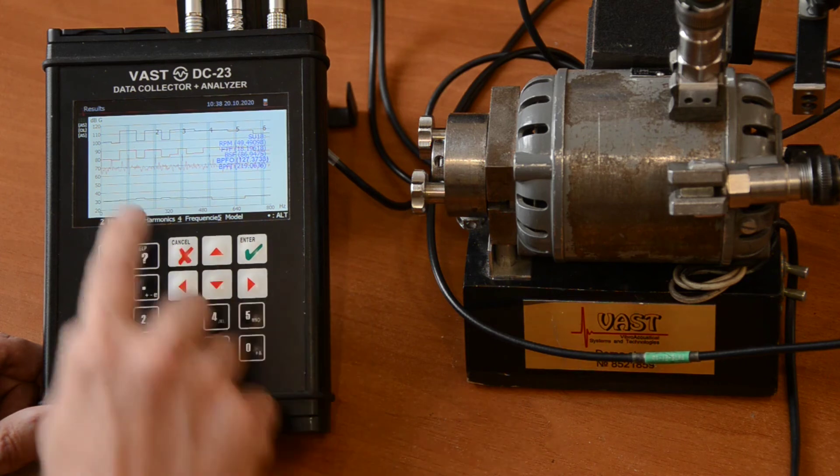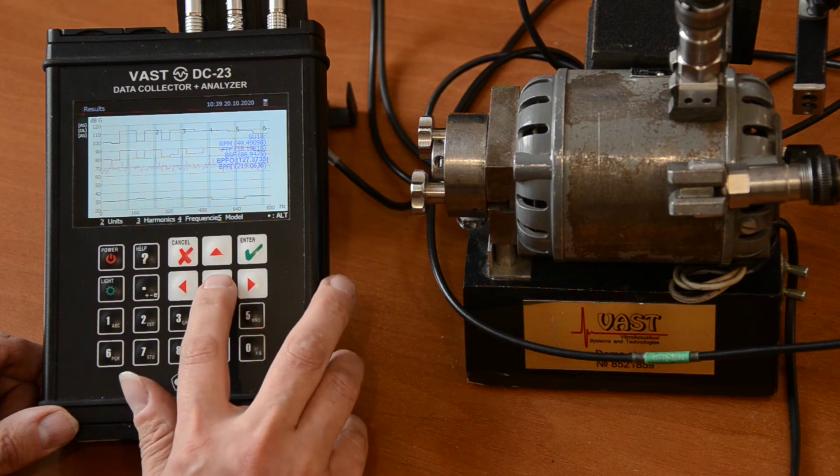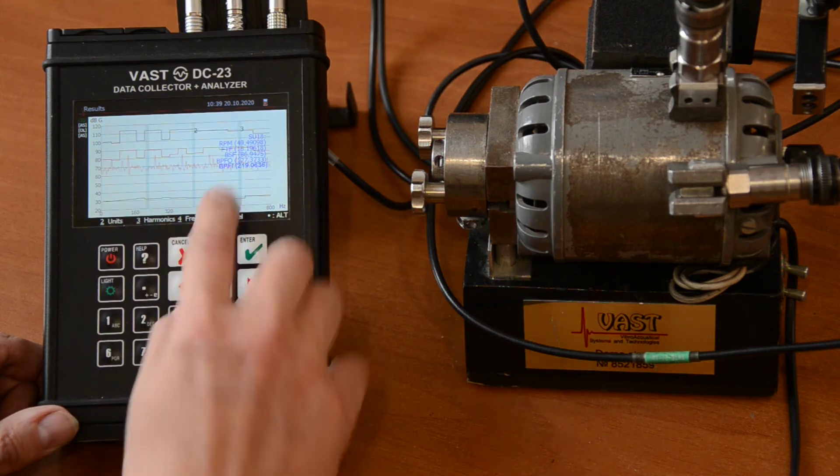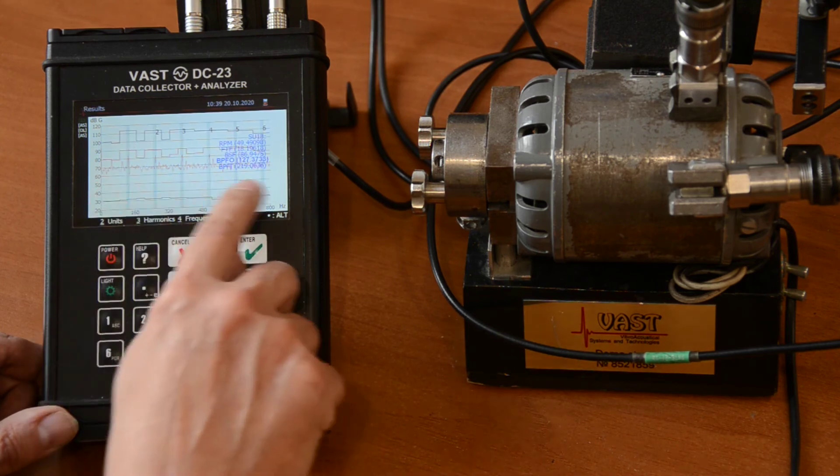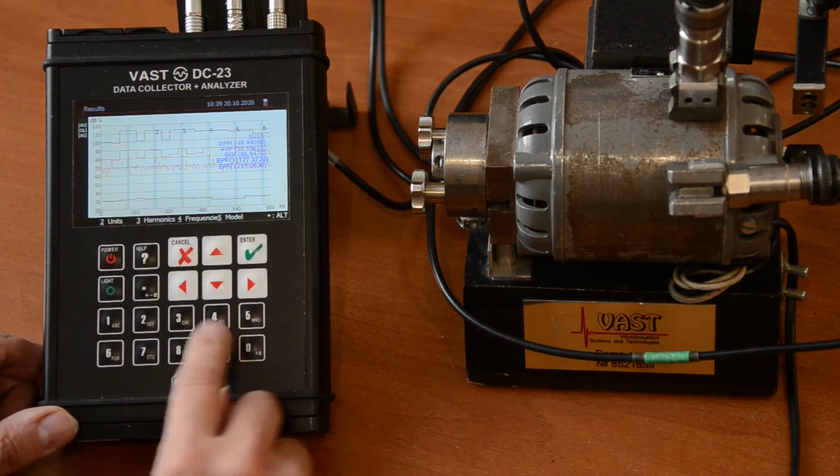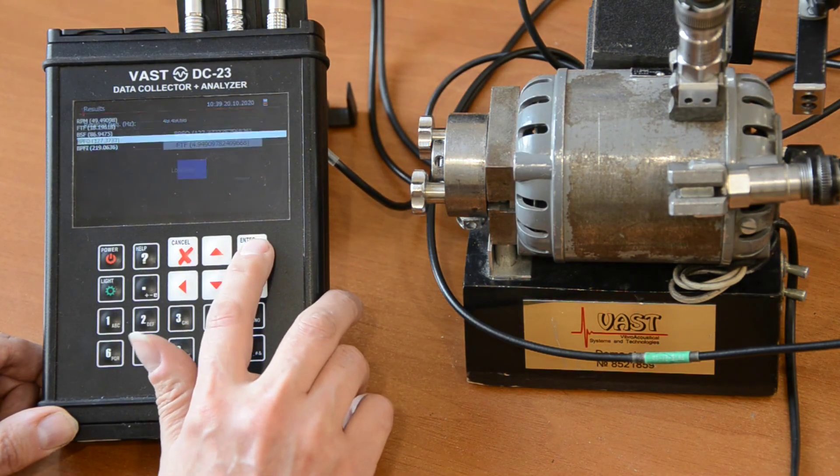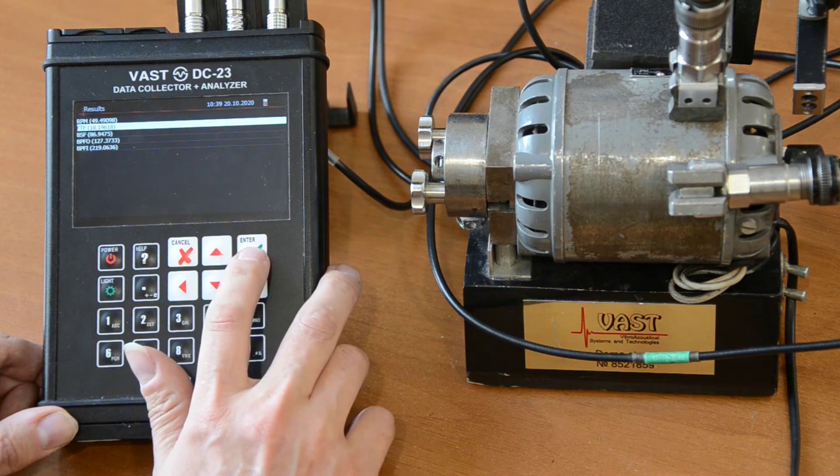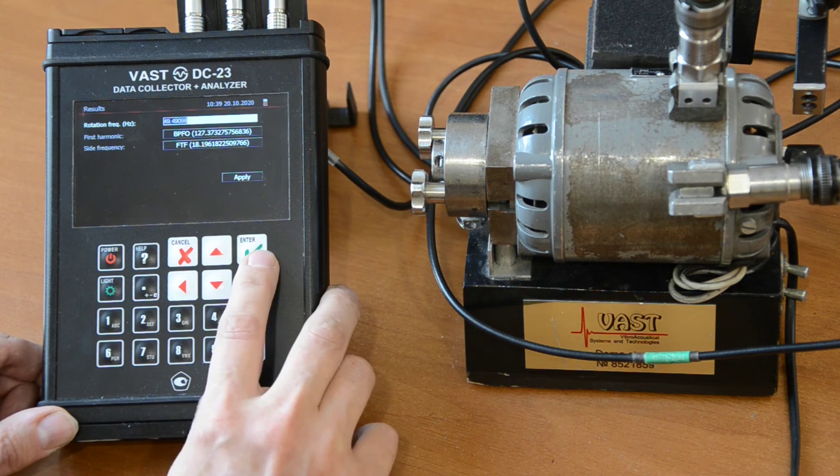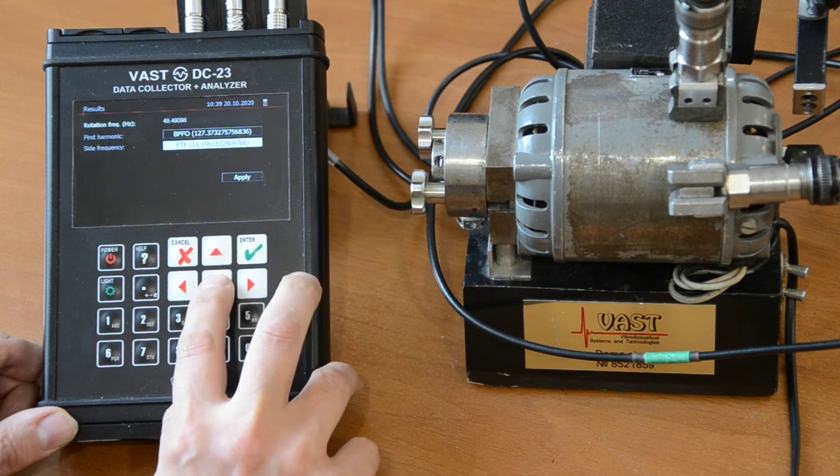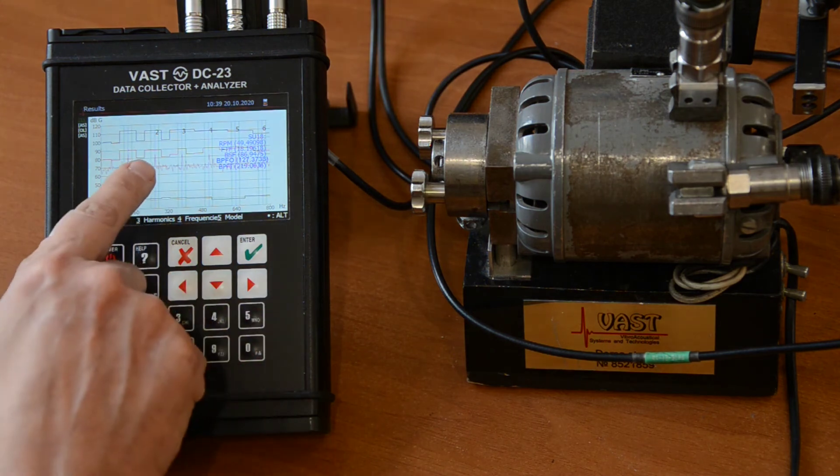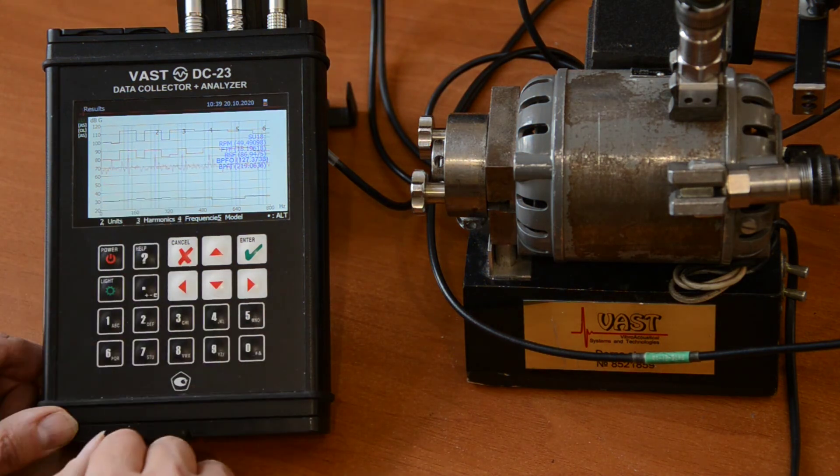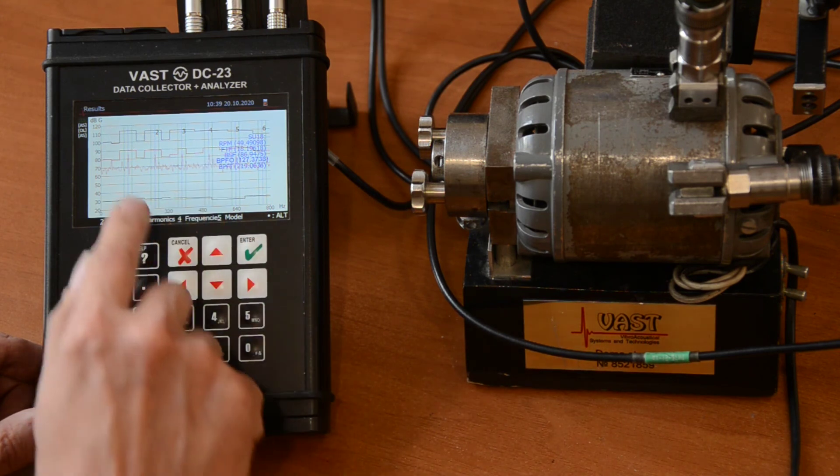Ball pass frequency, outer race. And we see the exact fit for all the frequencies. And we have BPFI. This is inner race. Not there. So, we can say that this is BPFO. And this is outer race defect of the bearing. We can also say that this is, for example, BPFO. And select the frequency of modulation. For example, we can select cage frequency. Fundamental train frequency. We apply it. And we see that we also have the fit for the cage frequency, or the fundamental train frequency.